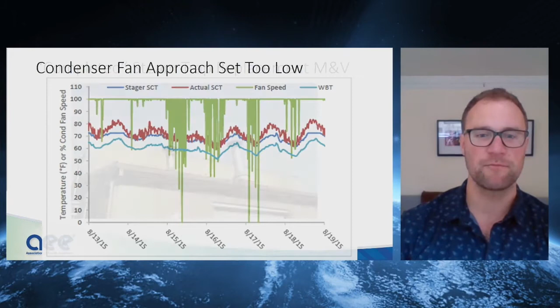But as you can see in red, that actual condensing temperature of the system just isn't able to meet set point most of the time because the condenser's undersized. Meanwhile, the fans are at 100% speed, as you see here in green, staying at full speed most of the time except at night, where it's actually able to meet the set point and the fan speed will drop. So it indicates a programming adjustment is needed. This graph only shows the pre, not the post, but you get my point.